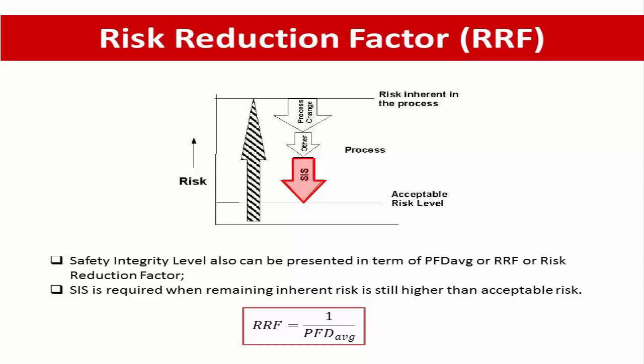This is the correct concept, however the state of inherent risk and acceptable risk is very hard to quantify. The way to quantify it is to measure the risk reduction capability through PFD, or Probability of Failure on Demand. It is assumed that the SIS, when properly programmed, can reduce the risk whenever it operates successfully in response to a process demand, but it will not reduce risk if it has failed. For low demand systems where hazardous conditions occur infrequently, PFD average is considered the inverse of the risk reduction factor.